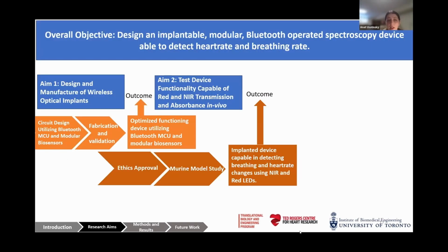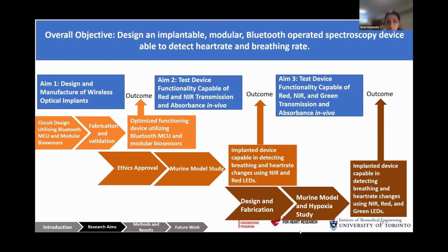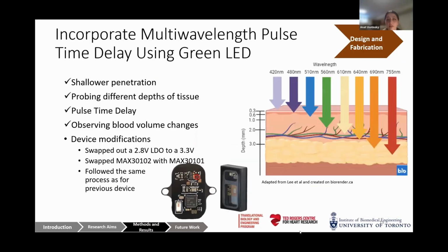Now that we have created a device that is capable of red and NIR transmission and capable of picking up heart rate and breathing rate, we decided to incorporate a green LED. And the reason that we would like to incorporate green LED is because the green wavelength has a shallow penetration. It allows us to probe a different depth of tissue, allows us to potentially do pulse time delay analysis, and it's good for observing blood volume changes.